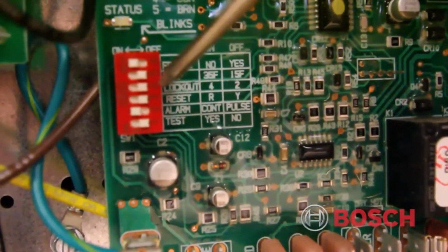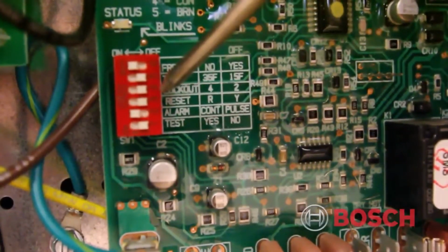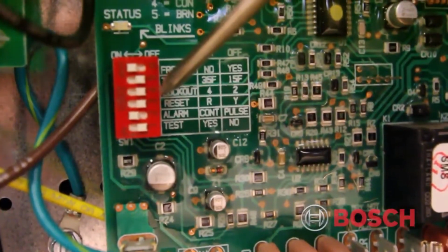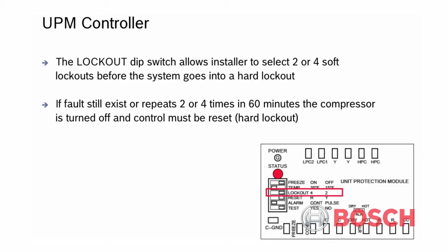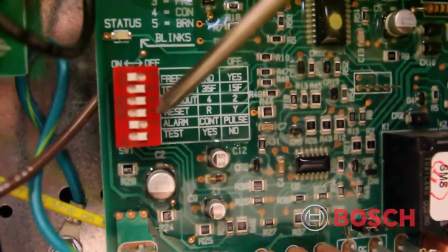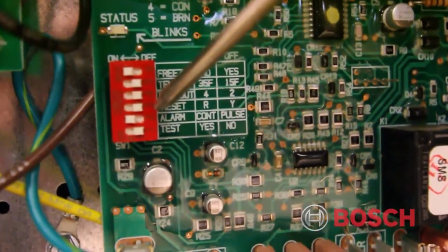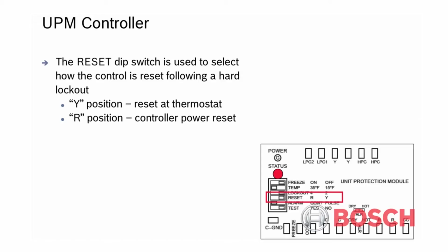Switch number 3 has to do with your lockouts. There is an option of 4 soft lockouts and an option of 2 soft lockouts before the system goes into a hard lockout. Switch number 4 is a reset option. In the factory position or Y position, you will be able to reset the hard lockouts from the thermostat. In the R position, the power must be reset in order to bring the system out of a hard lockout.